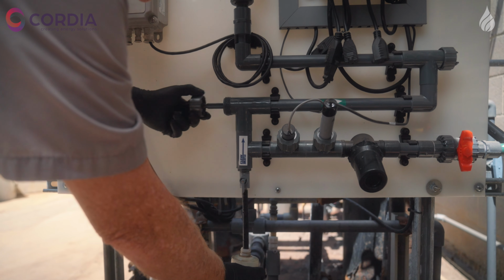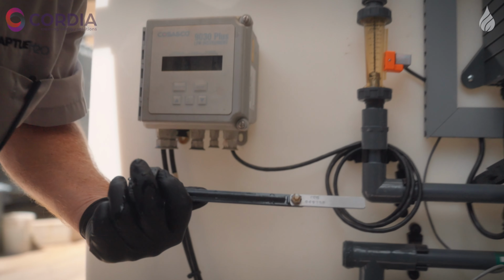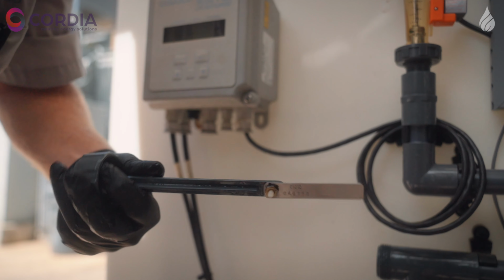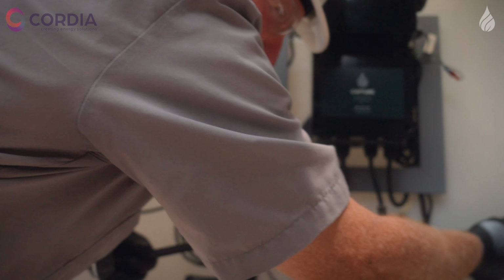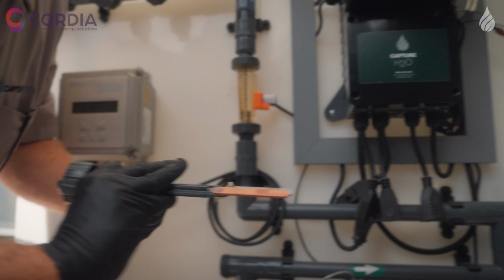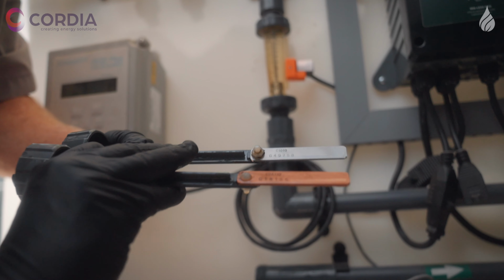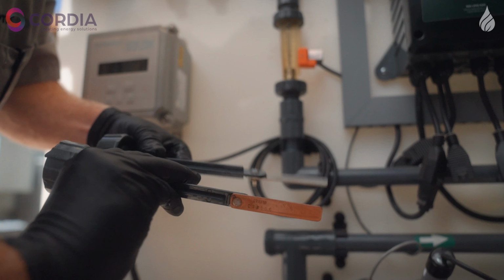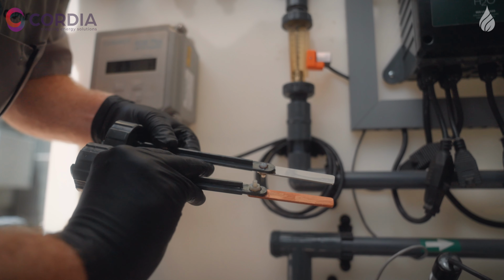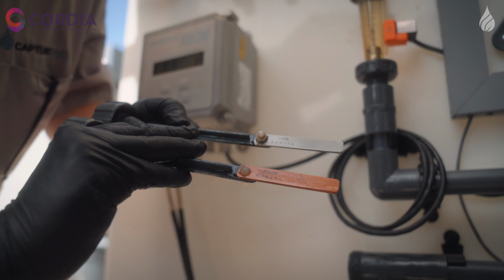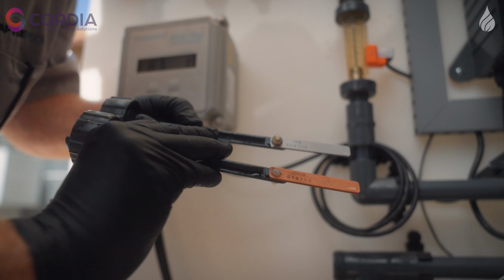How about the corrosion piece, how's that looked? The corrosion, I don't see anything on it. The tubes, whenever we do our eddy currents, they always come back good. The corrosion coupons we send in for testing and analysis always come back good. We actually have a third party other than Capture H2O that does a monthly test for us, and their test results have always been matching up with what we get from Capture.